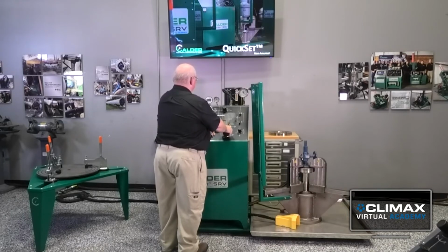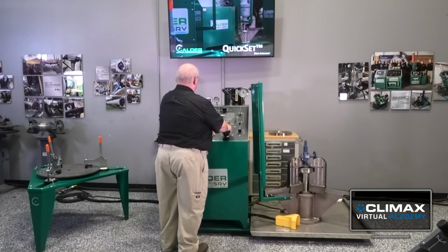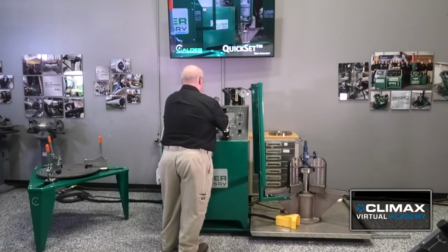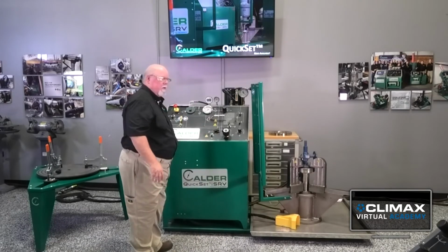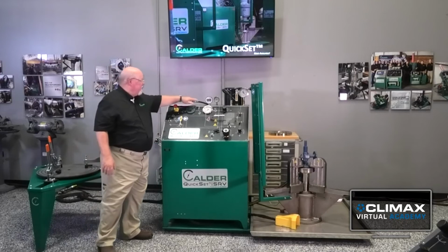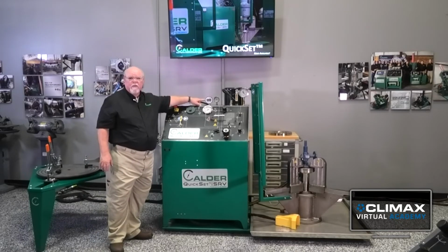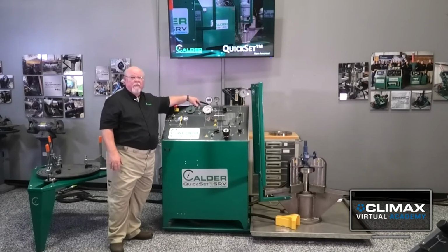I'm sitting right at 300 psi now, so I'm going to start bringing it up. I'm sitting at 330, 335, 340, 350, 360, 370, 380, 390, 400, 410. 415 psi is where the valve lifted. Now it closed and reset. I released the valve at 243 to give us some indication of that difference between opening and closing.